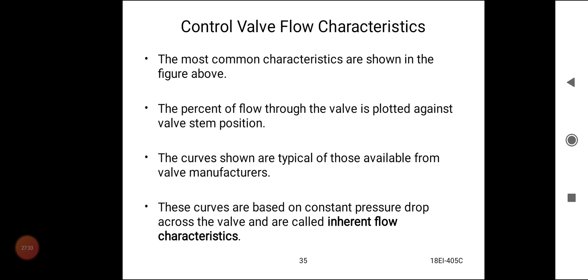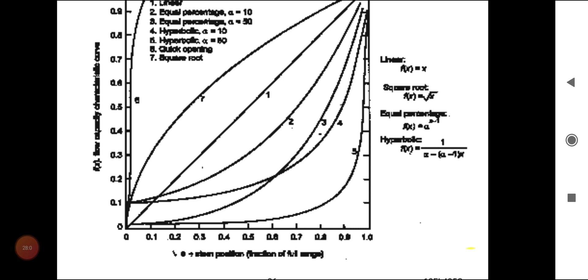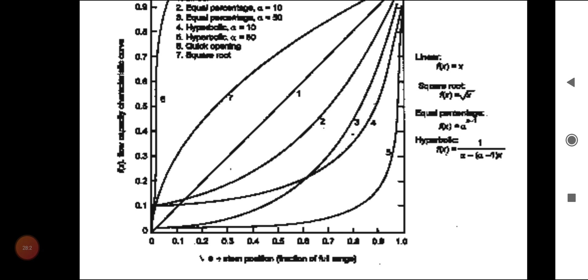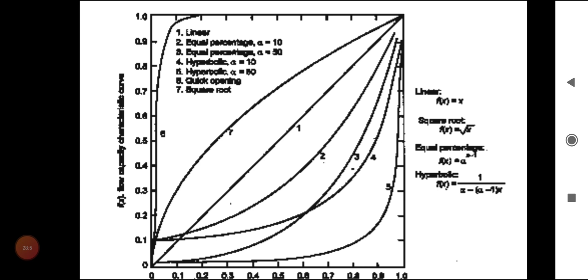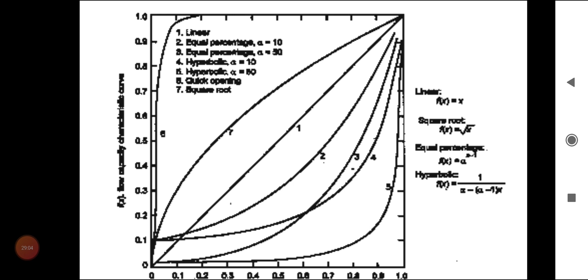So linear: f(x) = x. Square root: f(x) = √x. Equal percentage: f(x) = α^(x-1). Hyperbolic: f(x) = 1/(α-(α-1)x). So f(x) versus stem position is shown for equal percentage and hyperbolic with α equal to 10, α 50, and quick opening type. Graph 1 shows linear, graph 2 shows equal percentage where α is 10, the third graph shows equal percentage with α 50, hyperbolic with α 10 is the fourth graph, the fifth graph hyperbolic α 50, the sixth one quick opening type, and the seventh one shows square root.